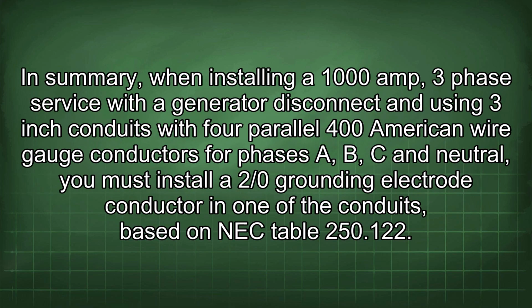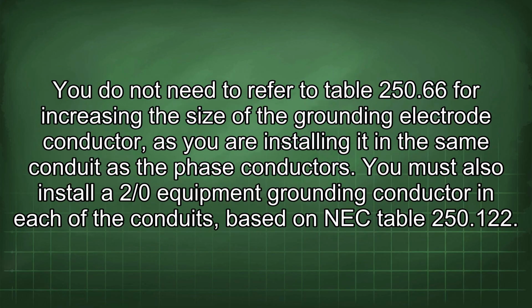In summary, when installing a 1000 amp 3-phase service with a generator disconnect and using 3-inch conduits with 4 parallel 400 American wire gauge conductors for phases A, B, C, and neutral, you must install a 2/0 grounding electrode conductor in one of the conduits based on NEC Table 250.122. You do not need to refer to Table 250.66 for increasing the size of the grounding electrode conductor, as you are installing it in the same conduit as the phase conductors.